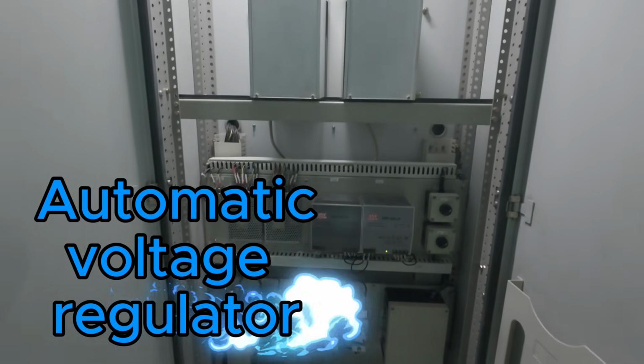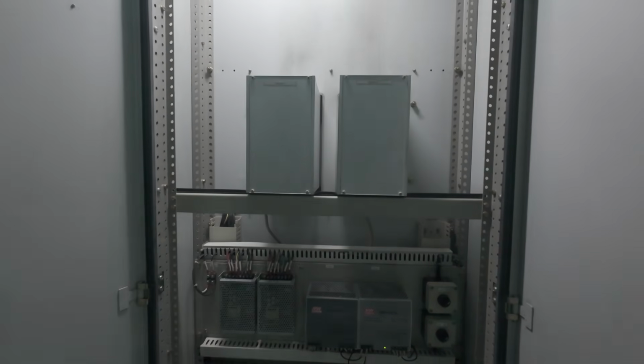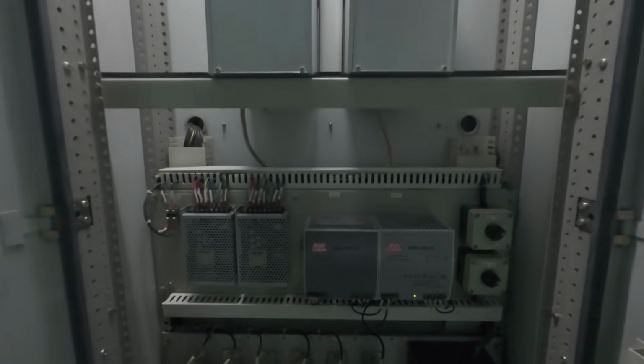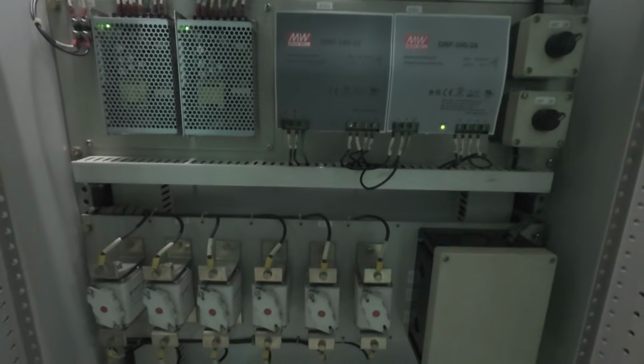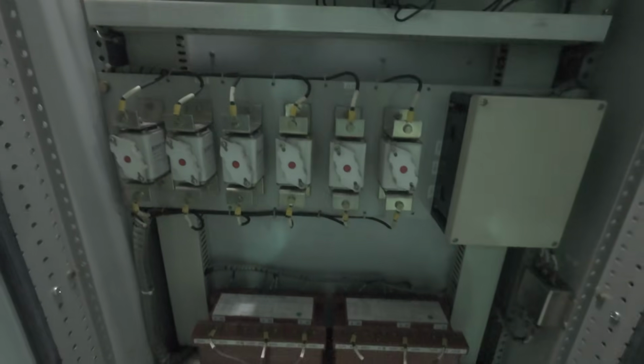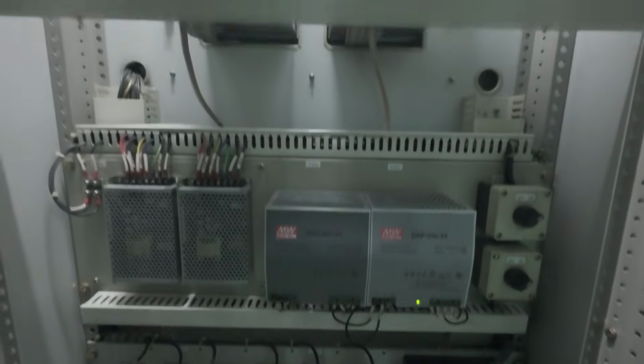Controlling everything is the AVR, the Automatic Voltage Regulator, the brain of the entire system. The AVR constantly monitors generator voltage in real time. If voltage drops, it boosts rotor current. If voltage rises too high, it reduces excitation. All of this happens automatically within fractions of a second.